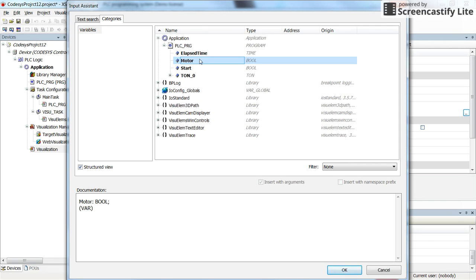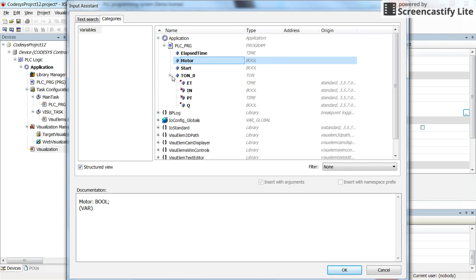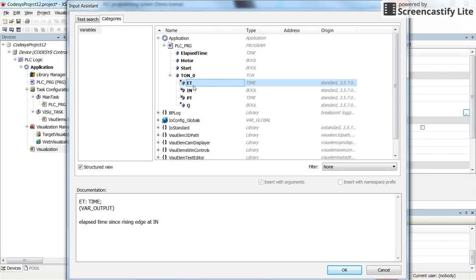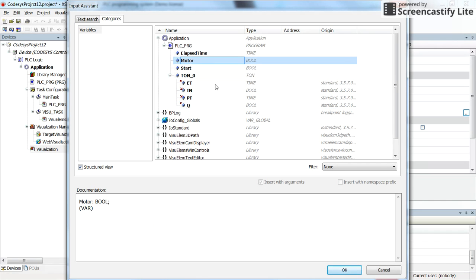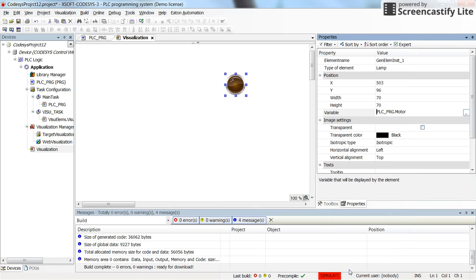Elapsed time, motor, and start are the variables that we have declared. TON_0 is another variable which the type of it is TON. As you pay attention here, you will see that there are sub-variables which belong to the TON. So here we have the elapsed time, we have the input preset time and output of the timer. We will use them later.